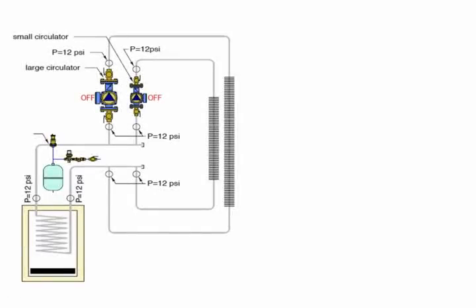Okay, I'm going to speed through this chart quickly, but to show you kind of the engineering side of what happens with pump conflict. Here's a system. It's a boiler, a high-efficiency boiler, and it's got 2 pumps, and it's all on one level, and these circles are pressure gauges. We're just going to pretend it's all on one level, and everything's off, okay? And the engineer has decided to pressurize the system to 12 psi.